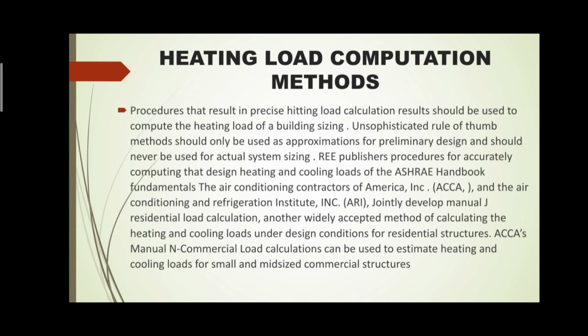ASHRAE publishes procedures for accurately computing the design heating and cooling loads in the ASHRAE Handbook of Fundamentals. The Air Conditioning Contractors of America, Incorporated, which is ACCA, and the Air Conditioning and Refrigeration Institute, which is ARI, jointly developed Manual J, residential load calculation, another widely accepted method of calculating the heating and cooling loads under design conditions for residential structures. So, etong mga institutes na to, gumawa sila ng bagong procedure para mas makompute natin yung heating load sa isang lugar. ACCA's Manual N, Commercial Load calculations can be used to estimate heating and cooling loads for small and mid-sized commercial structures. So, yung mga binigay nilang procedure, magagamit lang natin yon sa maliliit or sa mid-sized na lugar. Hindi yun pwede sa mga big buildings or yung malalaking bahay, for example.